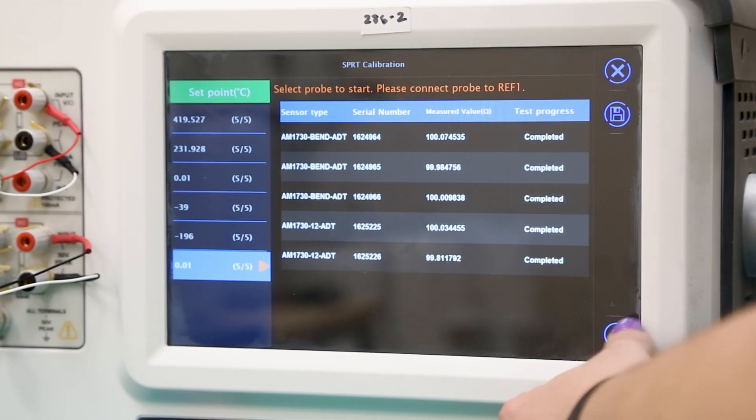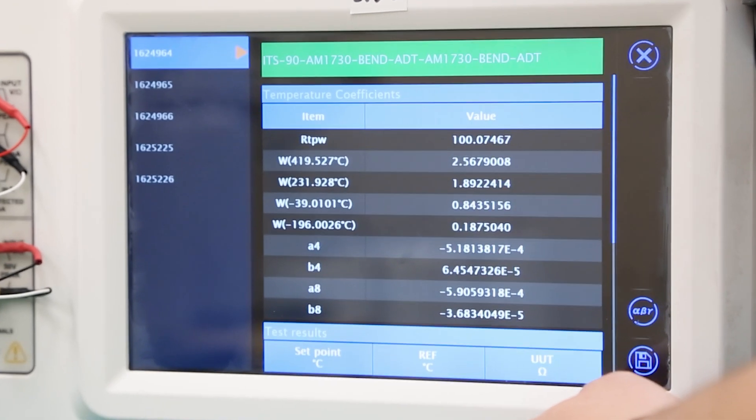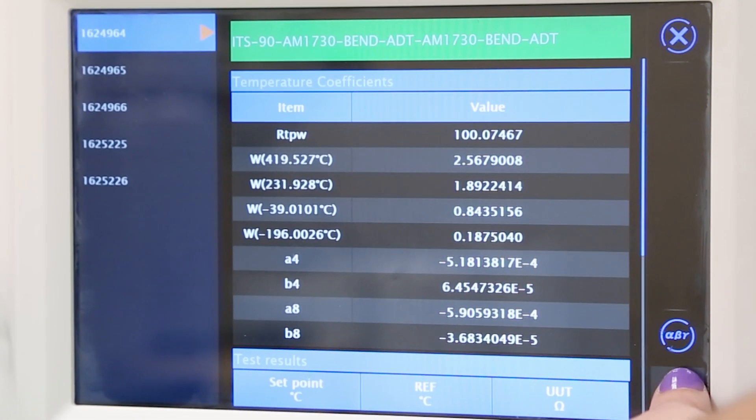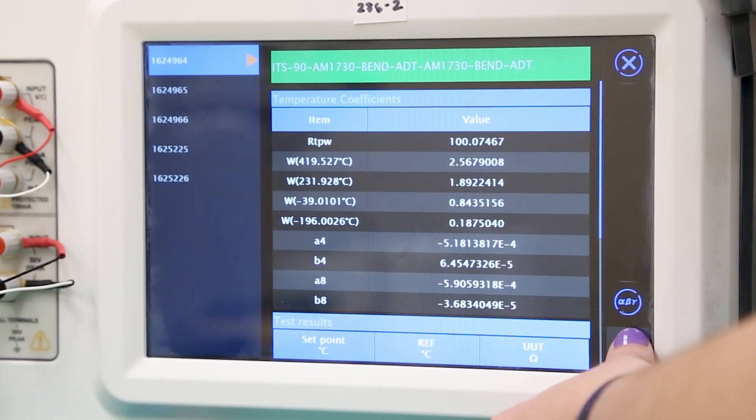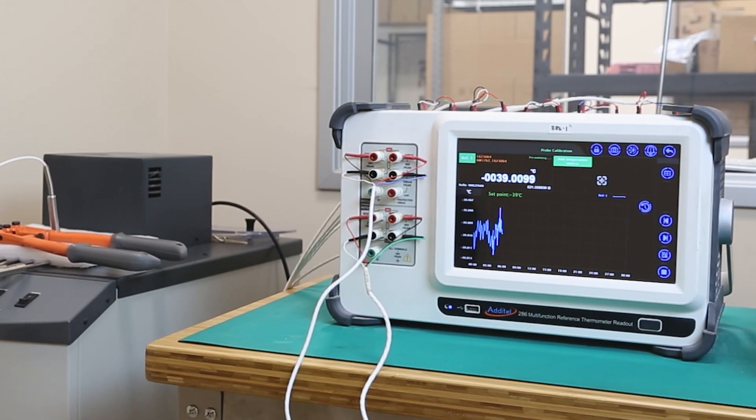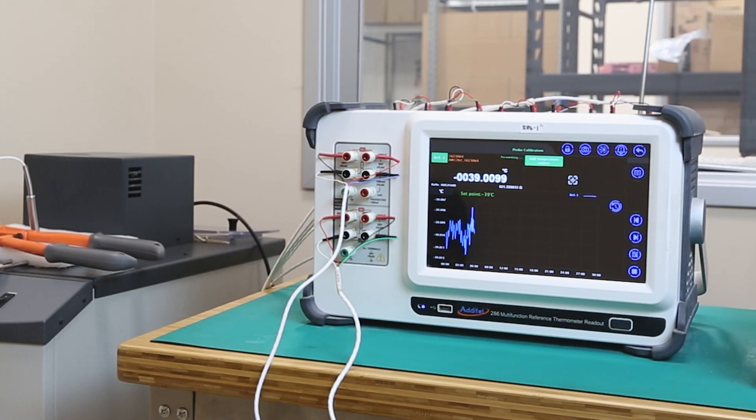Once all testing is complete, calibration results can be saved and reviewed immediately. The Additel 286 automatically calculates resistance ratios, ITS-90 temperature coefficients, temperature averages, and more, making it one of the most intuitive and easy-to-use electrical bridges on the market.